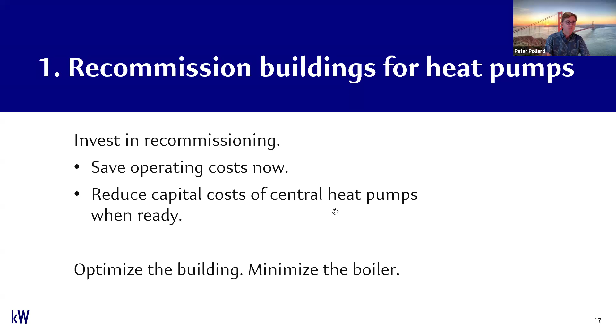What I mean here is applying a systematic methodology to identify, using data analytics preferably, critical zones, and then dealing with those zones as far as you can. By data analytics, I mean assuming a building with a BAS and some data from zones, rather than an approach where you just steadily reduce the temperature of hot water heating a building until someone screams, then address those cold people, hopefully on the coldest day of the year. It's a smarter, more systematic approach using actual data to understand what your zones are doing.